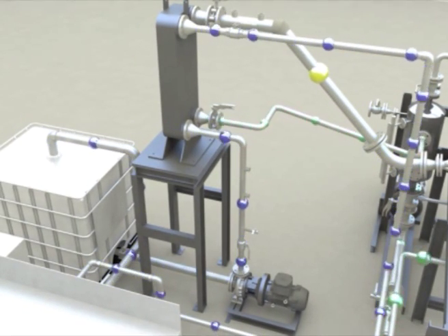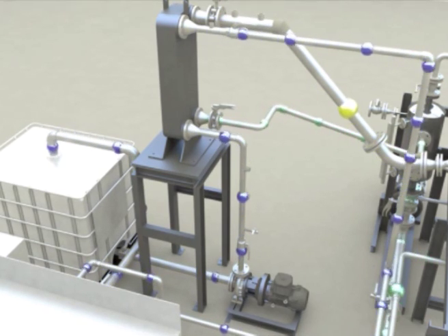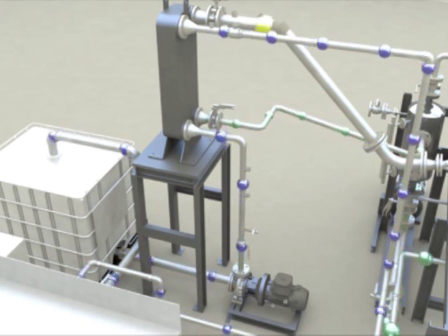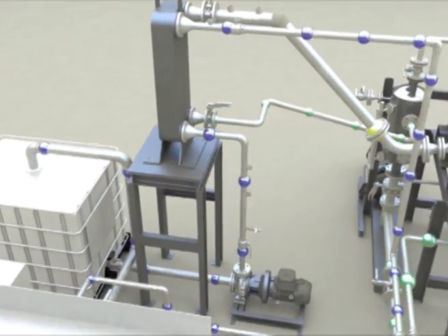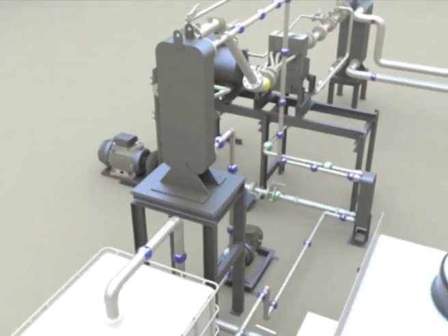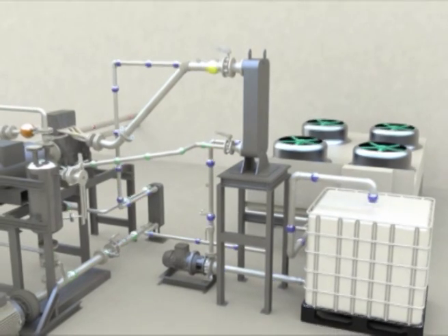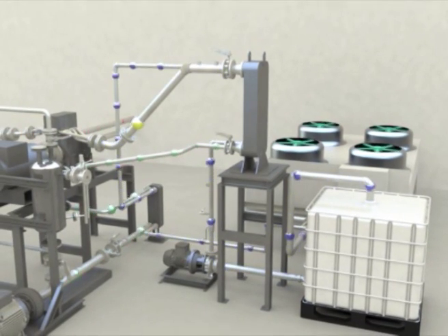The condenser utilizes cooling water to change the vapor back into a liquid. Thermal energy transferred to the water is then dissipated in this instance by an air cooler mediated by fans. The cooling loop is adaptable to the operating environment of the fluid engine, where the thermal energy can be used for secondary processes such as space heating, industrial process heating, or with absorption chillers.